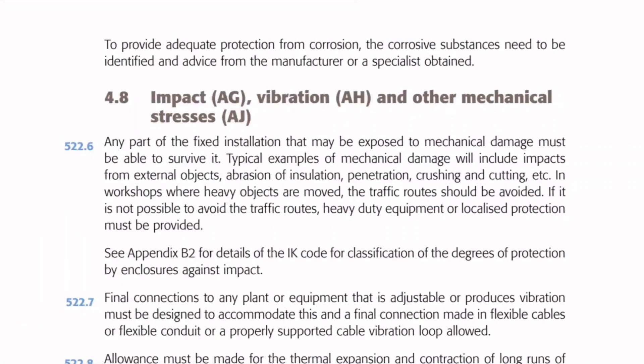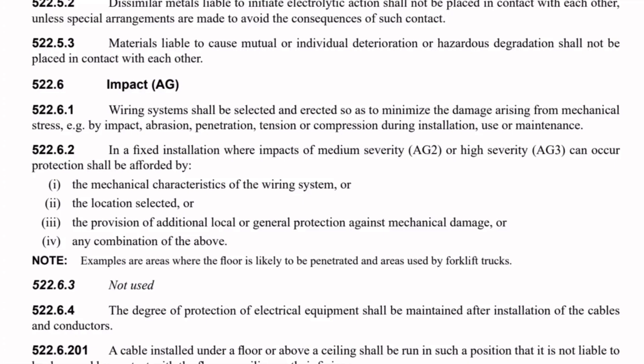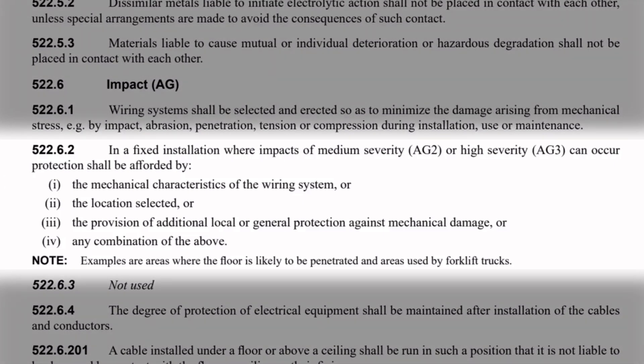Commenting on this, Guidance Note 1: Selection and Erection explains that any part of the fixed installation that may be exposed to mechanical damage must be able to survive it. Regulation 522.6.2 explains for areas of particular risk: in a fixed installation where impacts of medium severity (AG2) or high severity (AG3) can occur, protection shall be afforded by: 1) the mechanical characteristics of the wiring system; 2) the location selected — placing containment somewhere it's not likely to get struck; 3) the provision of additional local or general protection against mechanical damage, for example adding a sturdy steel barrier in front of the containment; or 4) any combination of the above.